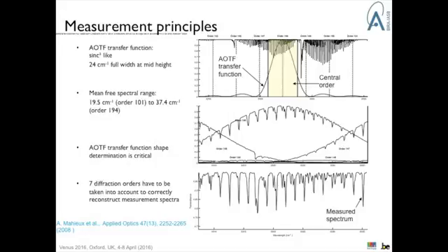Now the most complicated part of the instrument is the fact that, as I said, the filter was designed to let pass only one order. In practice, this filter, whose bandpass is reproduced here, is larger than one order. So here you have the spectrum we want to record. The box here delimits the order which was targeted, but in fact you will have information from 2 or more adjacent orders.